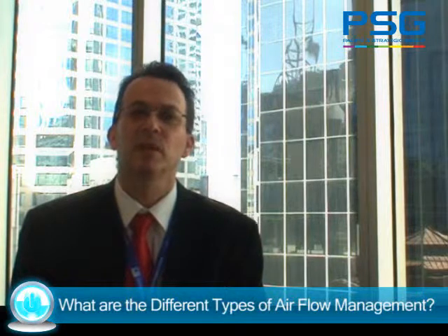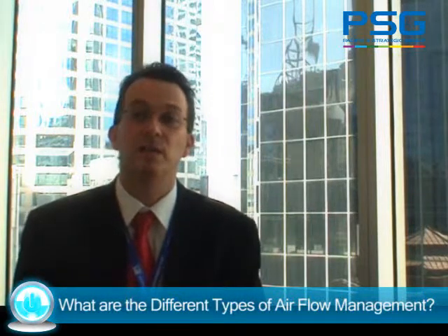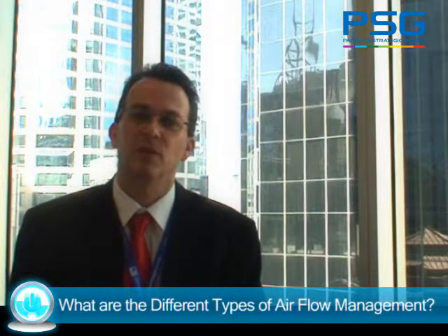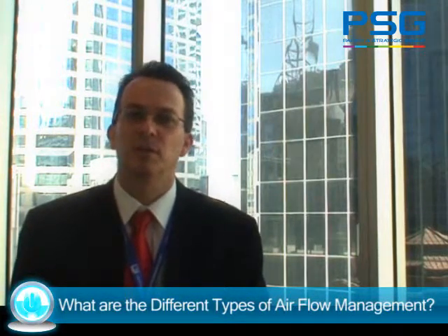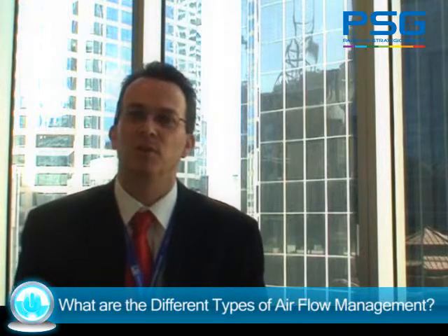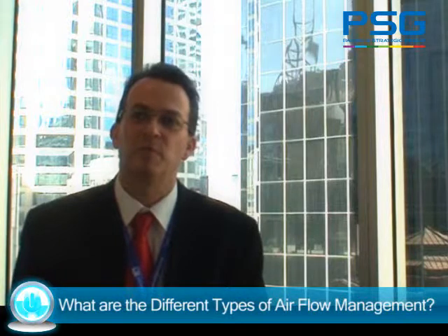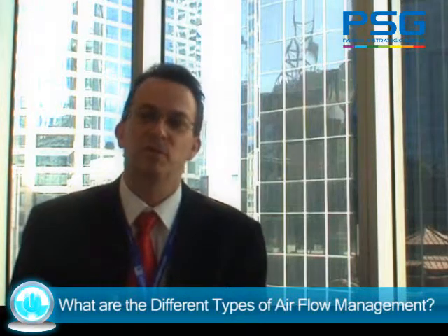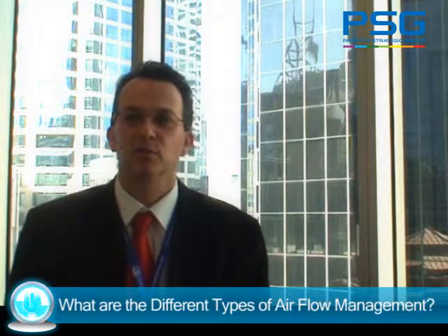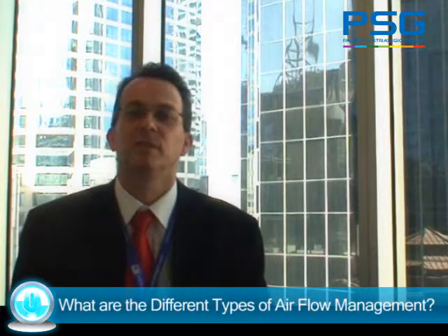In the future, what is happening now is to go to containment solutions, and there are many different solutions. They go from a cold aisle containment solution, where you have traditional rows of racks, and the cold aisle is contained, so the cold air can only go through the servers, not get mixed with the hot air. To cold air containment, so the air actually goes up into the rack from the bottom, with a solid front door on the rack. So that's like an inbuilt cold air containment but on the rack level. In that way, they're very easy to implement, because you don't have to change the room either way.